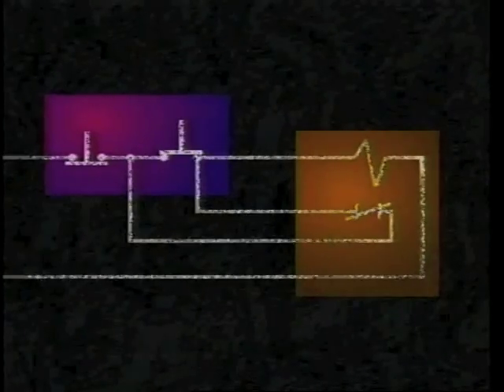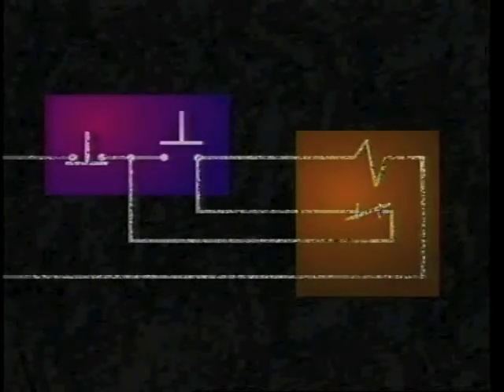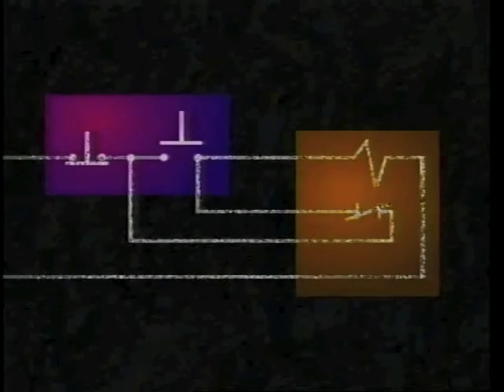Contactors are closed by manual operation of a remote control device, which energizes a coil. Once closed, they're held closed by this coil. Should a loss of power occur, the coil will release the contactor to the open position.